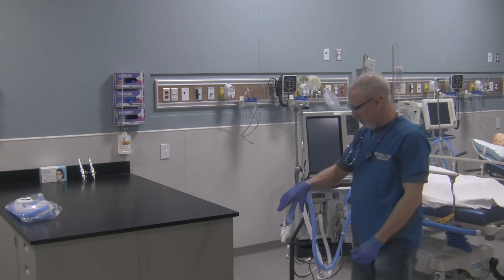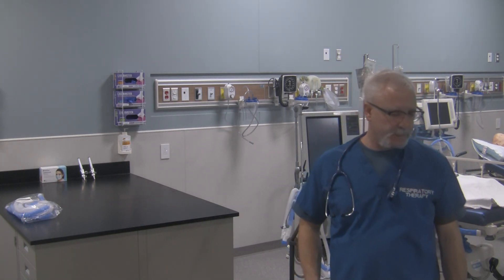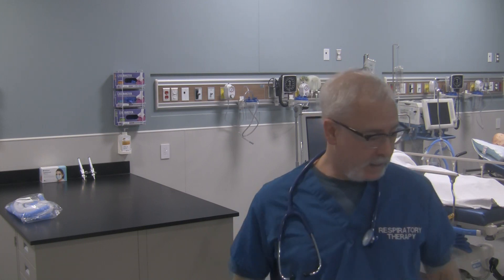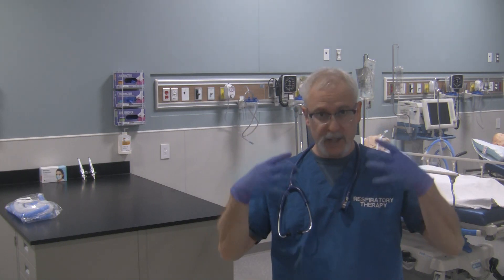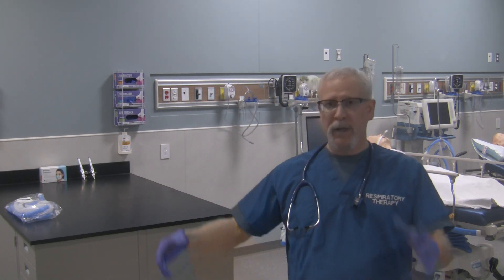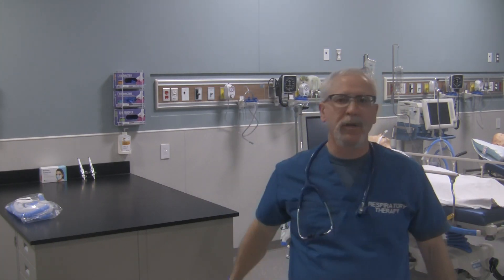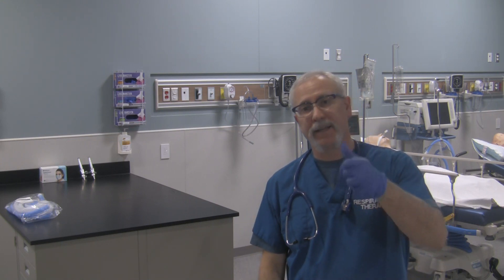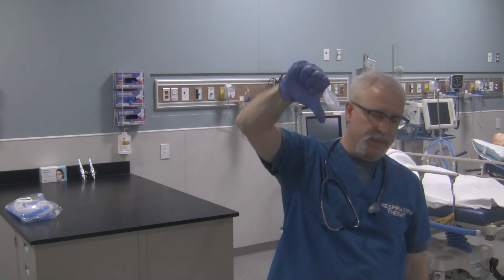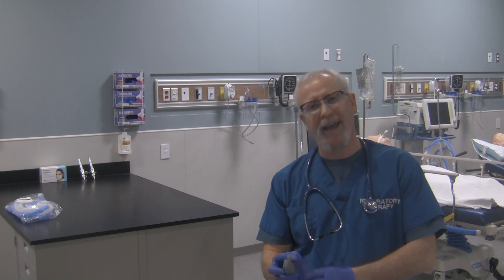That's pretty well how you circuit a PB840. When you're getting ready to use the ventilator on a patient, make sure you do the pre-use check, make sure the ventilator is clean before you circuit it. Gloves on, of course — make sure it's nice and clean for your patient. Don't let any of the circuit touch you anywhere — your head, your hair, the floor, the countertop. Assemble the circuit in a nice clean area, get it on the ventilator, make sure it looks neat and clean, and you're good to go. Hope you enjoyed this video — if you liked it, thumbs up. If you didn't like it, thumbs down, suggestions on how to improve it. Please subscribe to the channel, and have yourself one heck of a great day. George out.